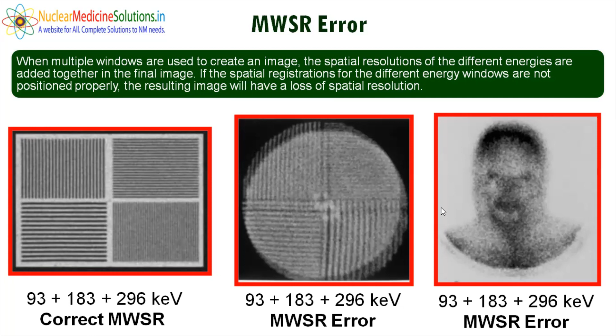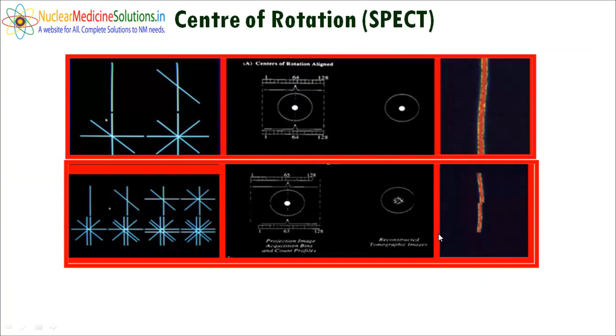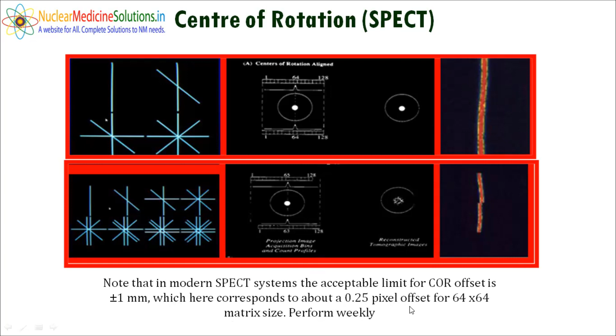Now, what is COR? We'll discuss the COR. If your COR, center of rotation, is okay, then we are getting a perfect sinogram of the data. If your COR is not okay, then it will produce an artifact or defect in the sinogram, and it will produce a ring artifact in your image due to the malfunctioning of the COR. The acceptable limit for the COR is plus minus 1 mm or 0.25 pixel offset for a 64 matrix size.